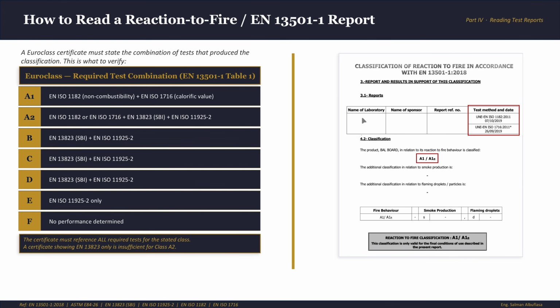It must list the name of the laboratory, the name of the sponsor, the report reference number, and the test method with the date. Verify every test method listed, and it should match the required combination for the claimed class. Then the classification states the class result. Then check the fire behavior, smoke production, and flame droplets table at the bottom. All three must be present. And read the final statement: the classification is only valid for the conditions of use described in the report. That means the exact product and the exact configuration tested, nothing more, nothing less. And it should be at the end.